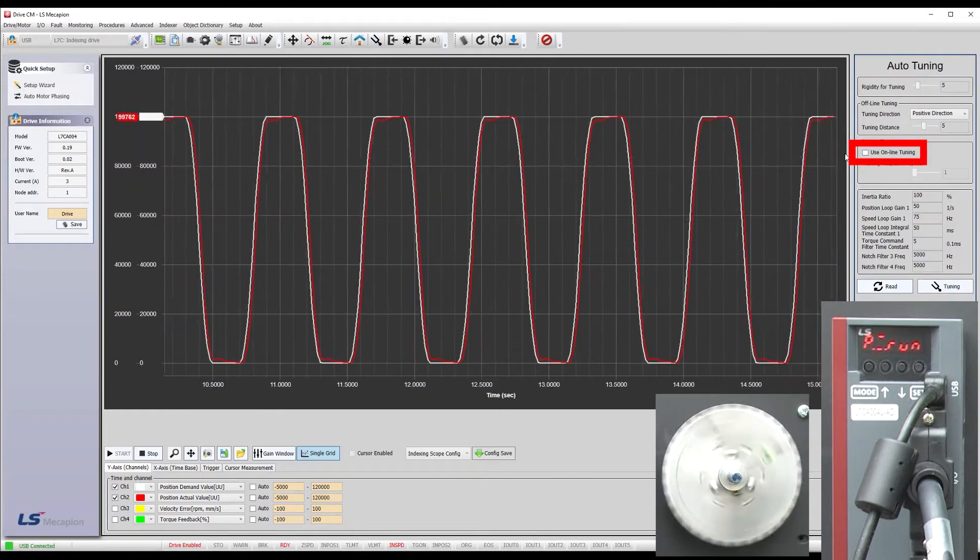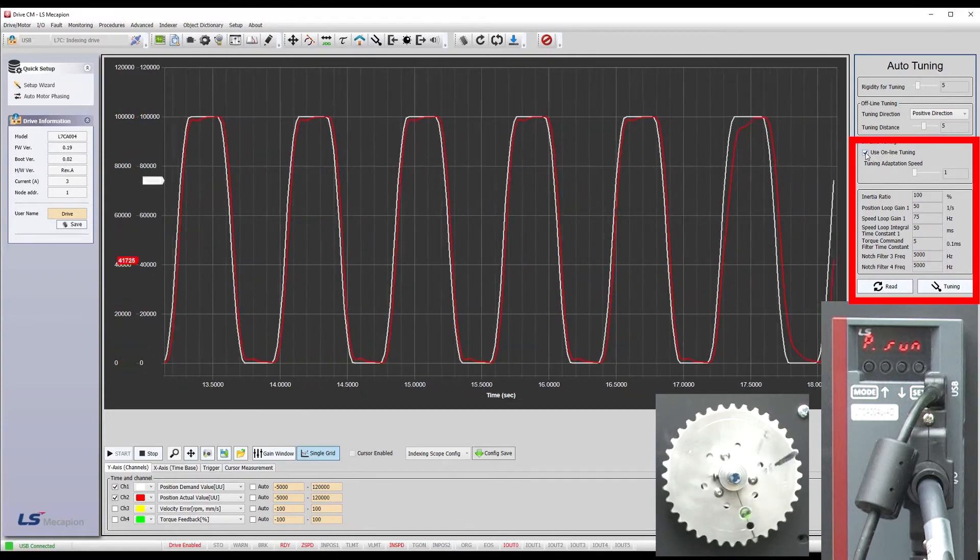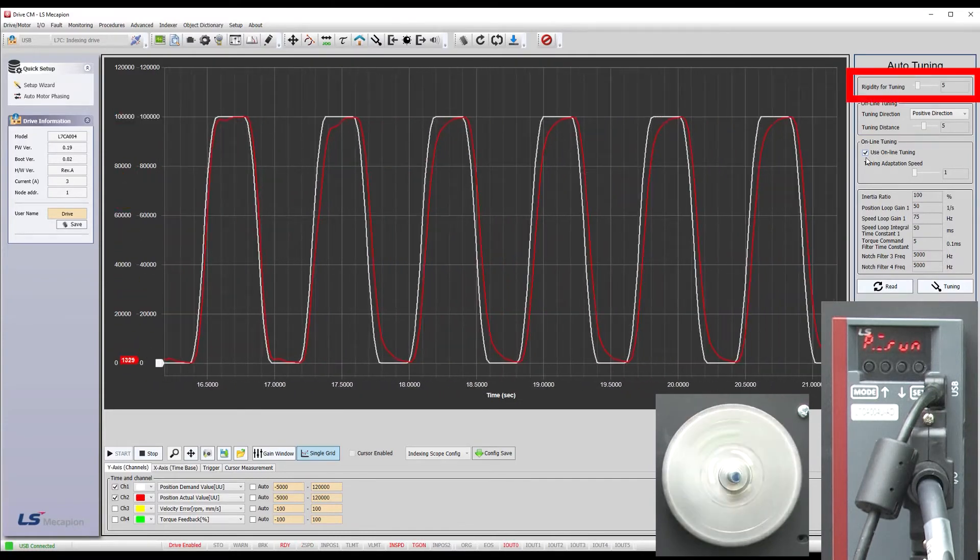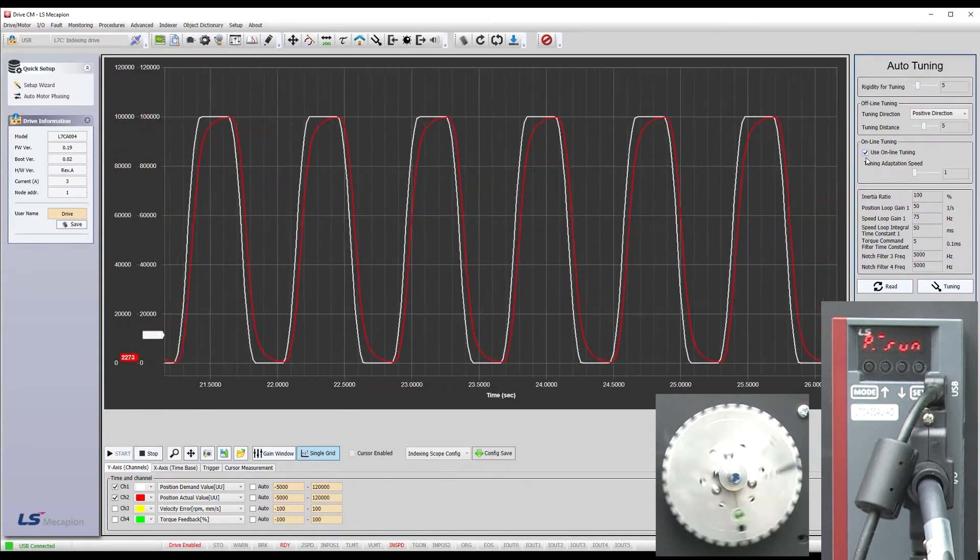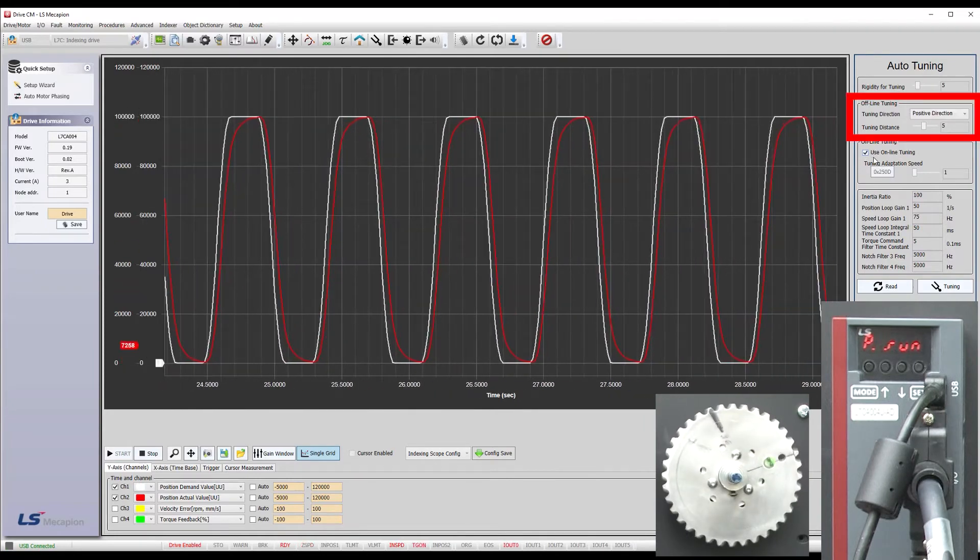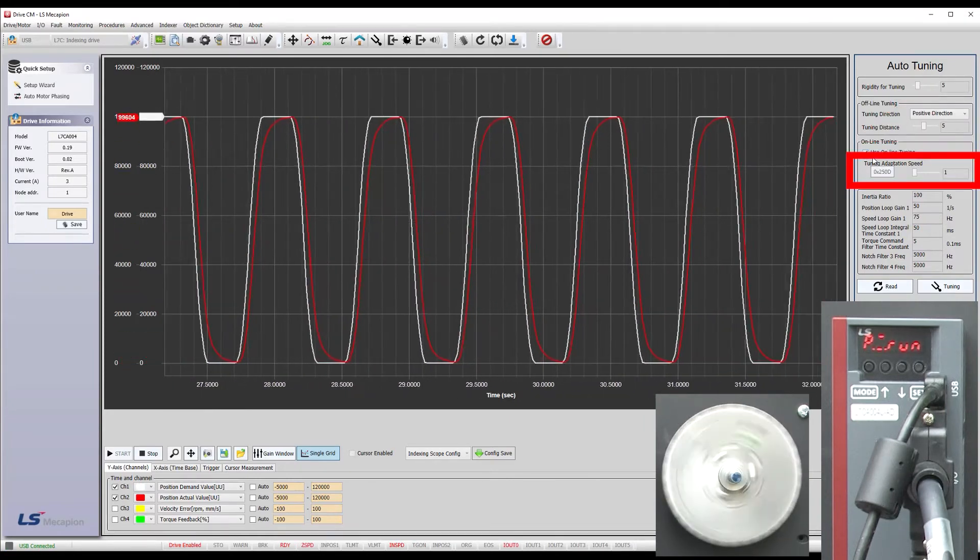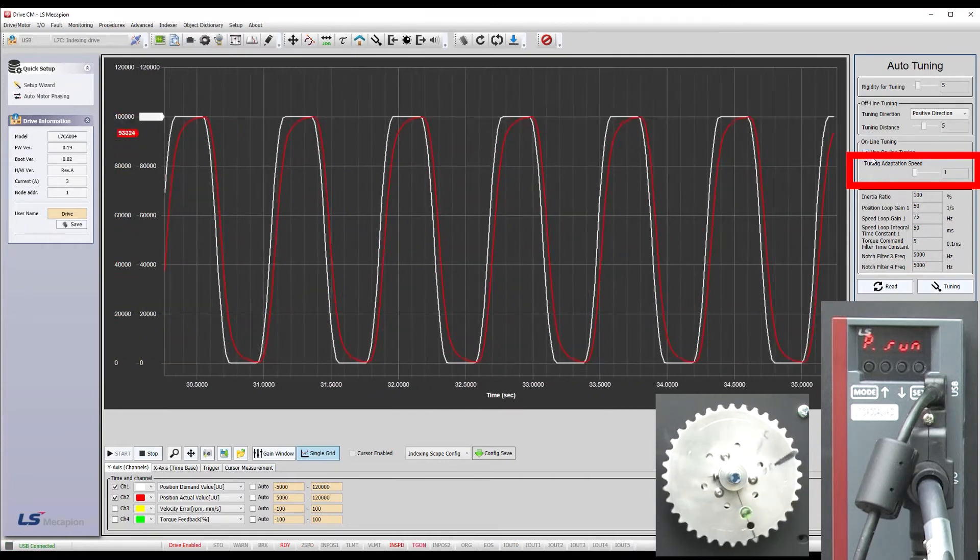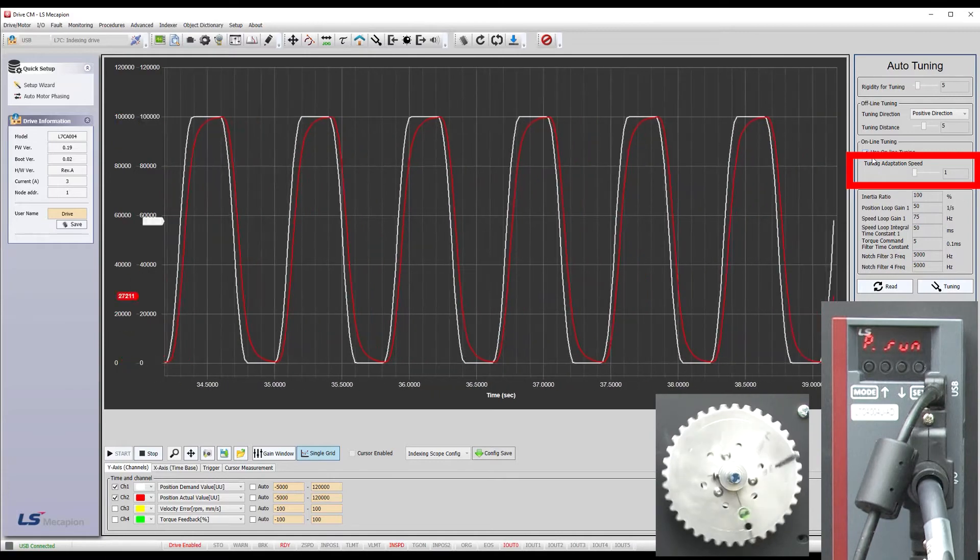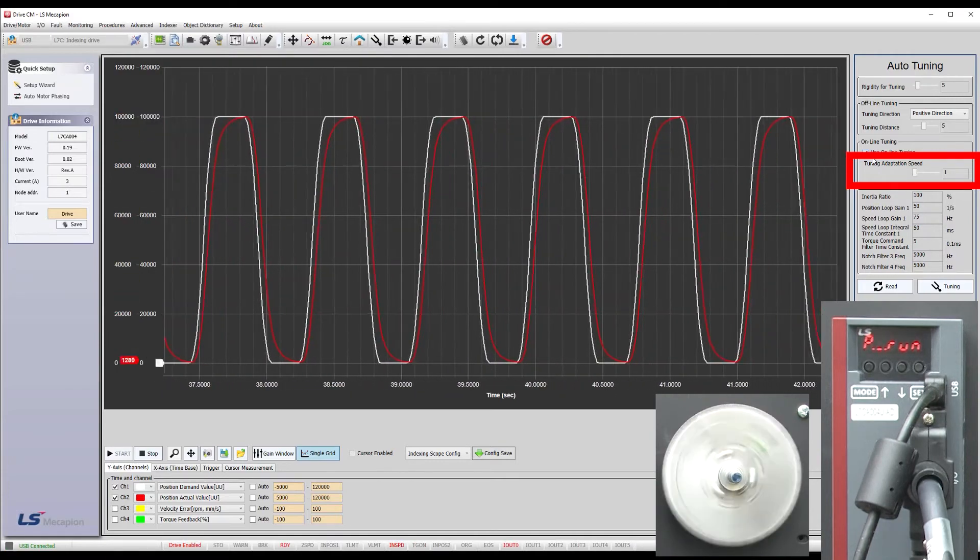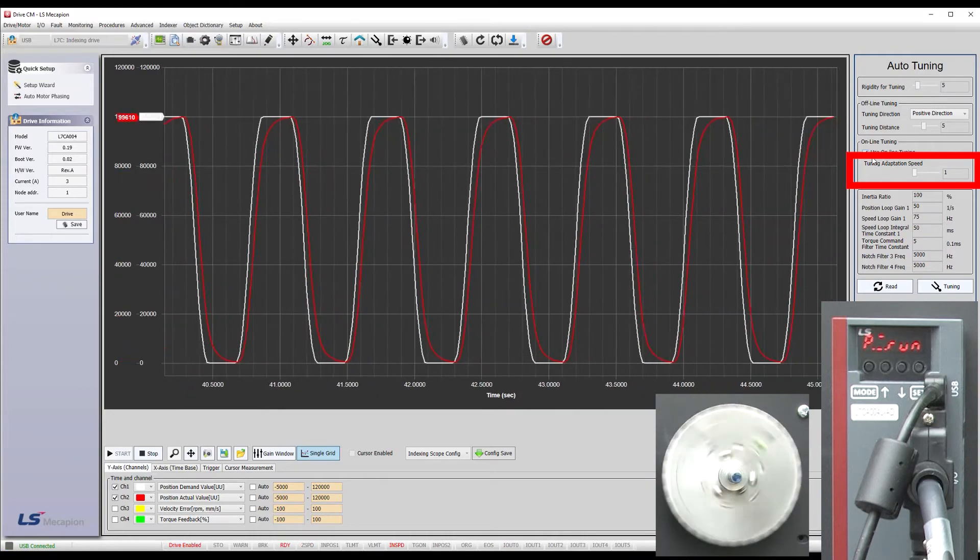Check this box to enable online tuning. As soon as I do that, the tuning changes because of how the rigidity is set up. In online tuning, we can control the rigidity and its adaptation speed. The distance is only for offline tuning and doesn't apply here. The adaptation speed is just how quickly the tuning adapts. Our demo is a fairly slow process so I'll keep that number small. You would only need to speed this up if you have a really fast process that you need tuning to adapt to really quickly.